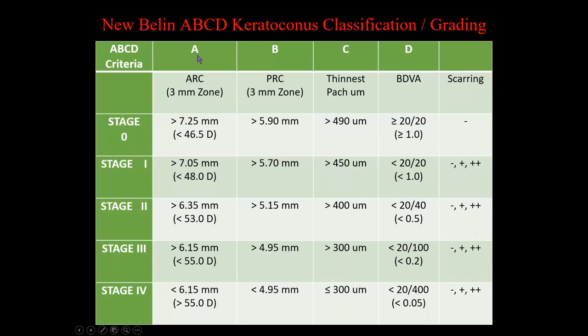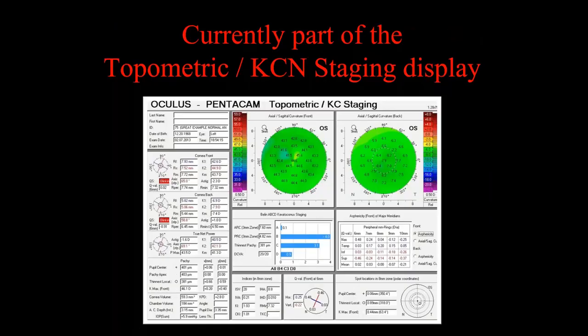To summarize: A stands for anterior radius of curvature taken from the 3mm zone at the thinnest point; B is back or posterior radius of curvature; C is corneal thinnest point pachymetry; and D is distance visual acuity — which the operator must enter, as the Pentacam doesn't measure it. We have stages zero through four. This is all done automatically and is currently part of the topometric keratoconus staging display.